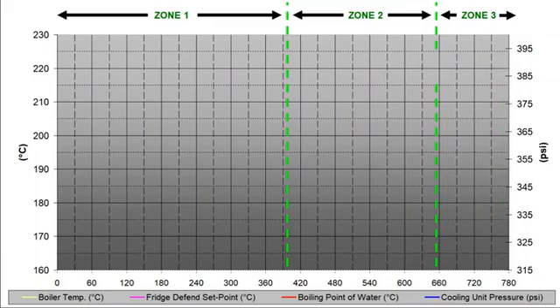Notice in the lower left corner the fridge heat source is started. The yellow curve measures the boiler temperature. The boiler temperature rises to a peak and then drops due to the boiler pump starting to pump refrigerant. The temperature briefly drops and then maintains steady state. Steady state boiler temperature is when the fridge is operating correctly and the fridge is completing its cycle.